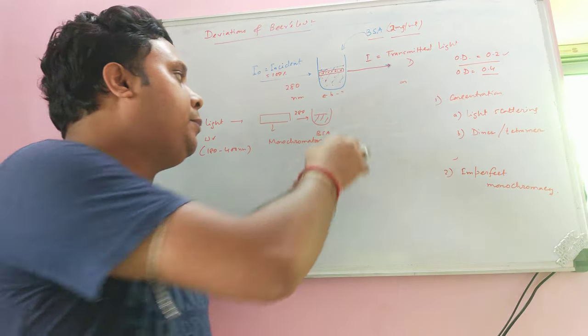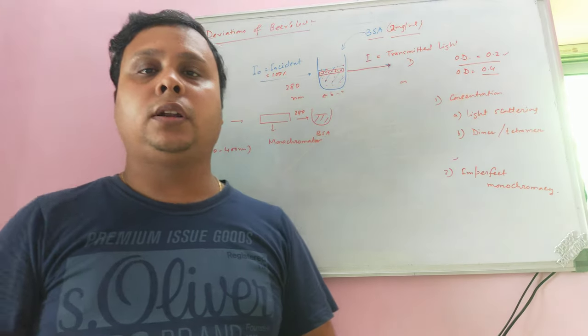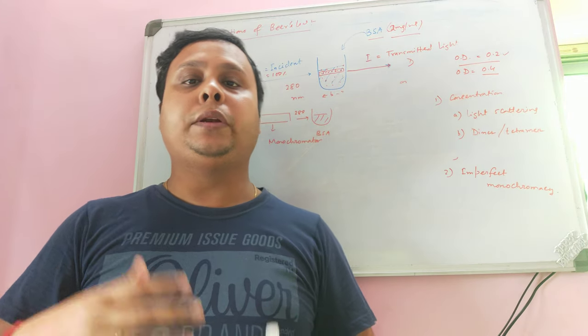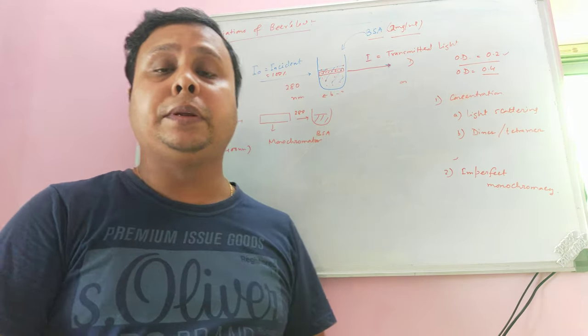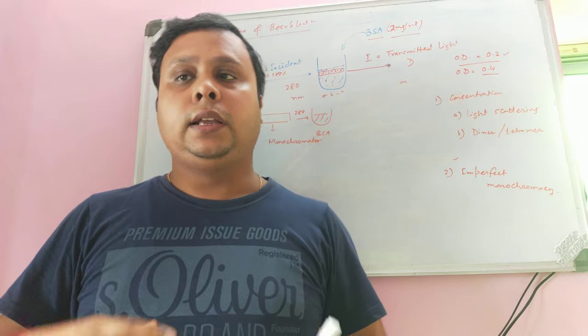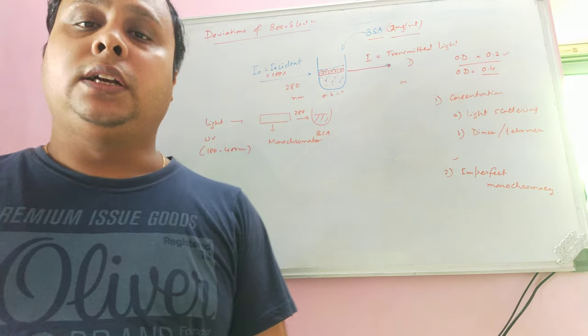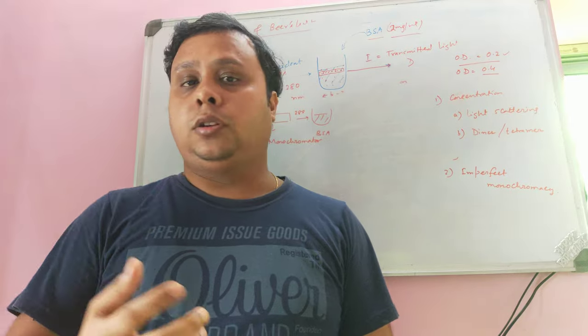As a result, the sample receives not only 280 nm but also perhaps 279 nm, 270 nm, 290 nm, and so on. This leads to deviations in the actual OD value. This is the second deviation: imperfect monochromacy.